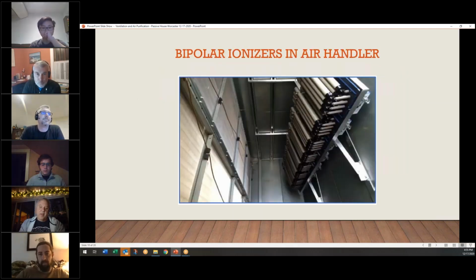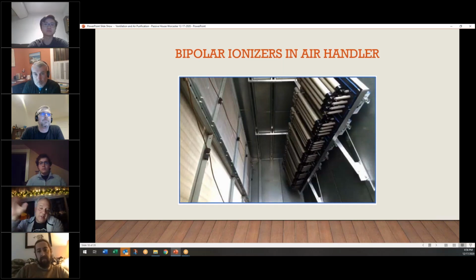All right. Now this is a very big installation, but this should be a supply plenum. That might be a heating coil there, because I see the freeze stat tube, or maybe it's an averaging one. The air would come out from the left, enter that supply plenum and then drop down to the airflow. Obviously on smaller systems, it may just be one of those tubes sticking into the side of a duct. You drill a hole, you stick it in, and this is obviously a pretty sizable air handler, because that's quite a number of ion tubes.